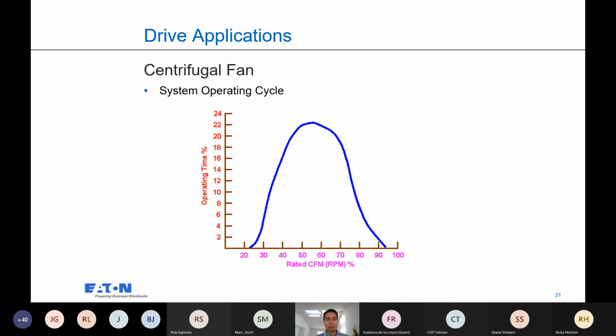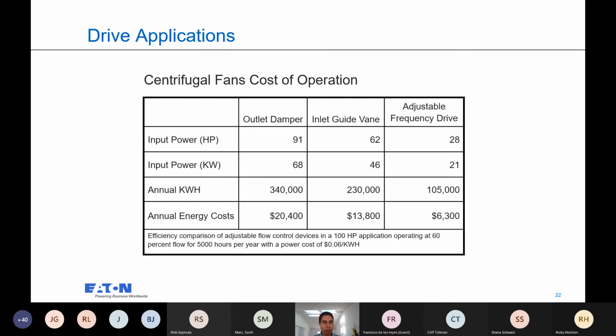Most fans, pumps do operate at partial loads. So I will go into this further down the line with slides, but a critical thing we need to think about here is let's look at our pump curve and let's analyze what the minimum speed should be applied onto your VFD for safety and to avoid any issues with your system. So now that I'm focusing on energy savings, let's go back to the slide here.